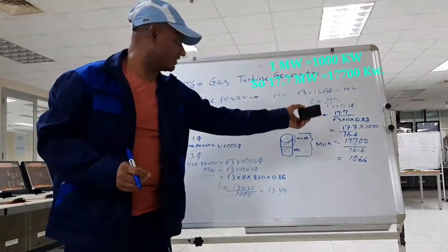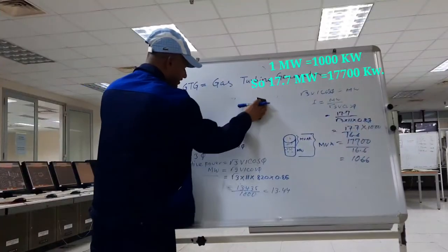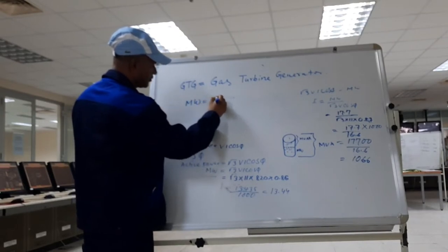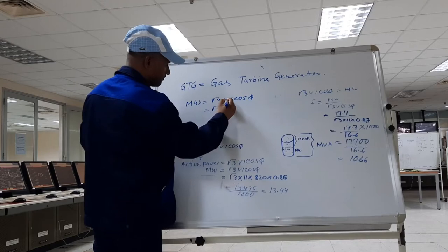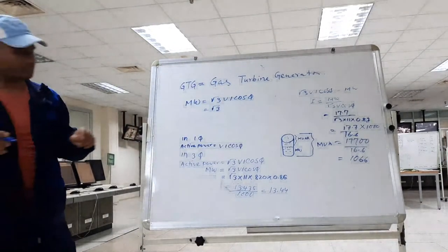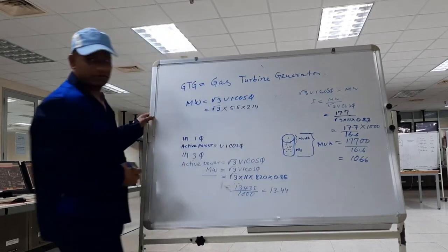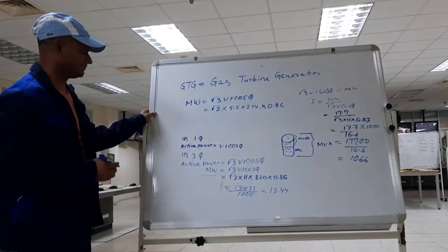So this is 11 kV; you calculate 11 kV like this. Now if you calculate our CCW pump, how much is the CCW pump current? Let me give one calculation. CCW train 1, one motor, this motor current is 214. But now I want to know how many megawatts this motor is taking. So you know the rule, root 3 V I cos phi. Voltage means this is the 5.5 kV bus bar, so 5.5, and the current 240, and power factor 0.86 around.